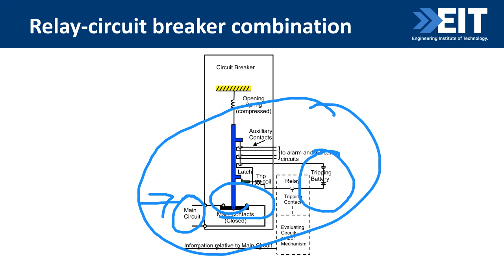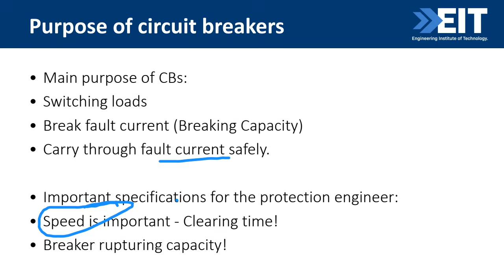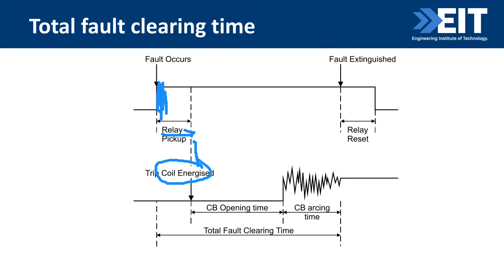Purposes of circuit breakers, obviously switching loads, break the fault current, and carry through the fault current safely. And obviously, as I said, speed is really important. And I'm just going to quickly show you the diagram for speed, why there's a problem here. Can you see this diagram here? The fault occurs here. There's a pickup of the relay there. So the relay picks up there, and the trip coil's energized at this point, and there's obviously a bit of arcing going on as the contacts are separated, and then the fault is extinguished, and then the relay is reset.